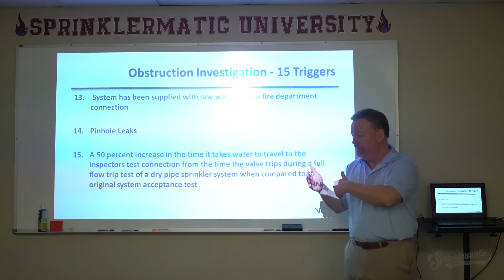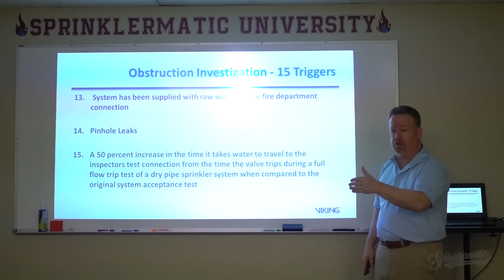I can tell you also that when you're comparing fire pump test curves, you're going to have to compare back to the original approving documentation for the system. So it's really important that we have that information available to us as well. Because if we've increased by more than 50%, if I started off with 60 seconds and all of a sudden I'm up to 100 seconds to deliver water there, that triggers an obstruction investigation.